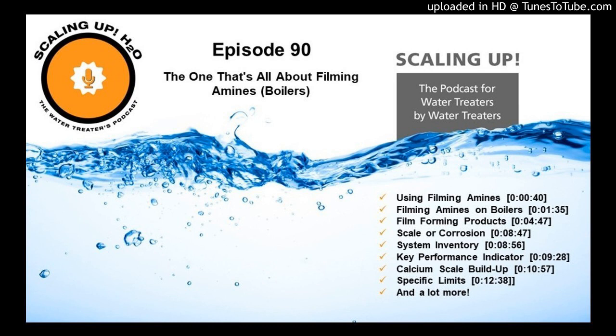your iron or your metal of interest. You're going to watch it climb, right? So you're going to have done a baseline measurement of whatever your iron rate is at that moment before you start the chemistry on. And then you're going to turn it on to either 50% of your theoretical loading, or a quarter of your theoretical loading, and you're going to watch your iron climb, and climb, and you're going to call your vendor and say, what gives?